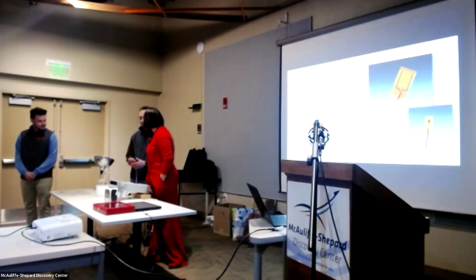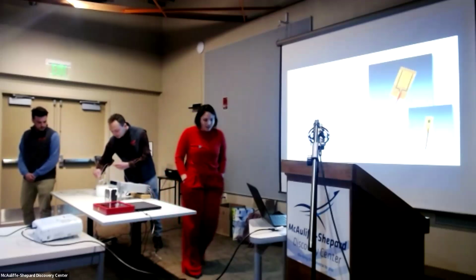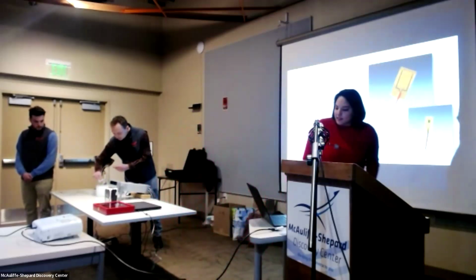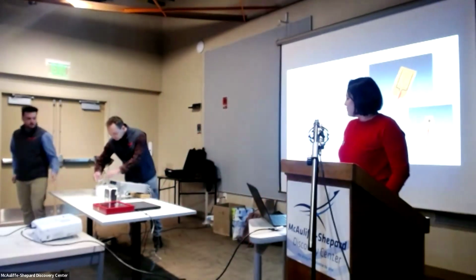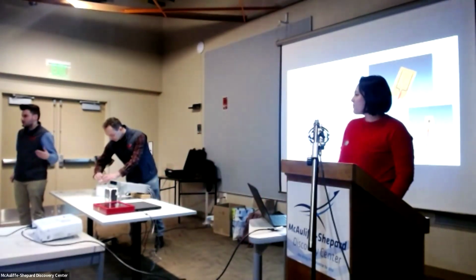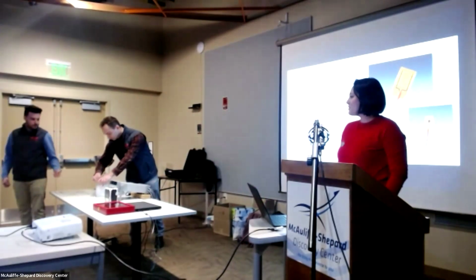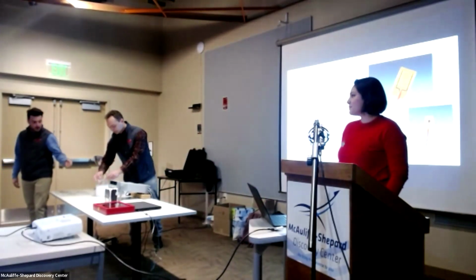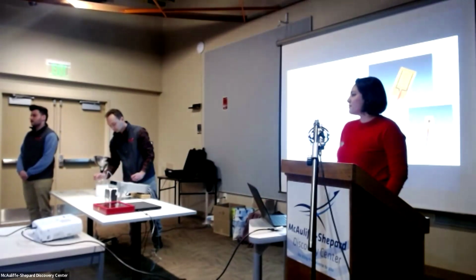You want to immerse it? We'll see if it should get down there eventually. So you can see as we took that sensor out, we rebounded back to about 32 degrees, a much higher temperature than when we had taken the metal RTD out of the dry ice.